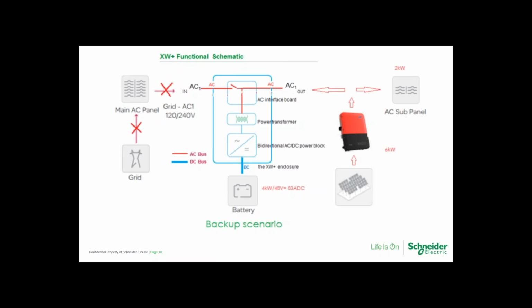However, I guess the challenge there would be, if you're grid connected, then you're going to typically be UL 1741 or even UL 1741 SA compliant. So let's say you have convinced the local authorities in Hawaii or California to allow you to AC couple with a UL 1741 SA compliant inverter, and the grid goes down, and then the XW shifts the frequency up. Well, part of the new smart grid functions is frequency ride through. So that range is typically 62 to like 68 hertz. So allowing the frequency to increase that high would have a negative effect on loads.